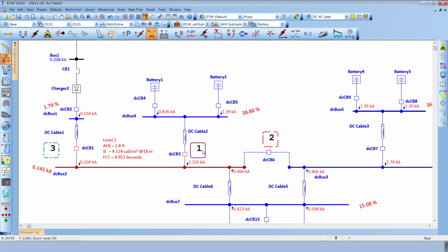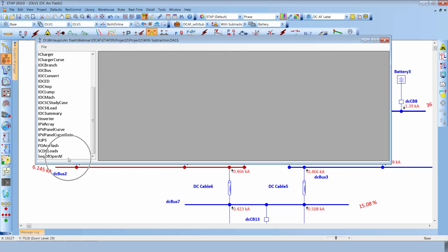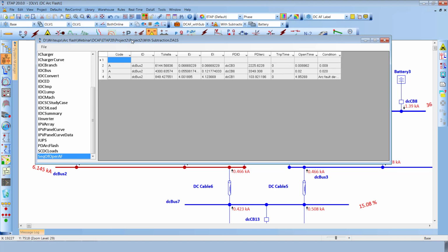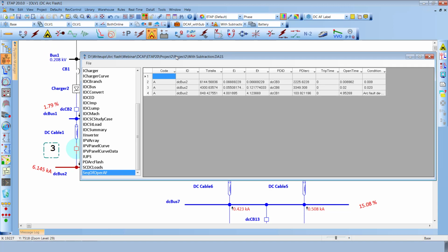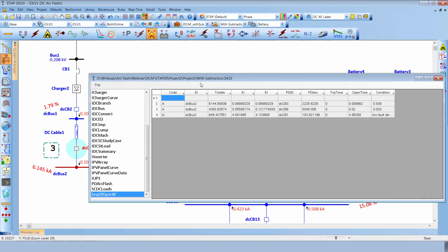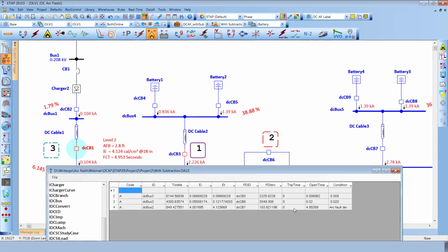The sequence of operation of events, depending upon the time at which each source path is de-energized, can be visually documented or seen from the report database. Upon clicking the report database under the subtraction report, the following sequence of operation table is created for users to examine the stage-by-stage calculation of incident energy from the point of initiation of the fault until the last protective device has operated. In this example, as you can see, the first protective device that cleared the fault coming from battery 1 and battery 2 is acknowledged to be DCCB3.